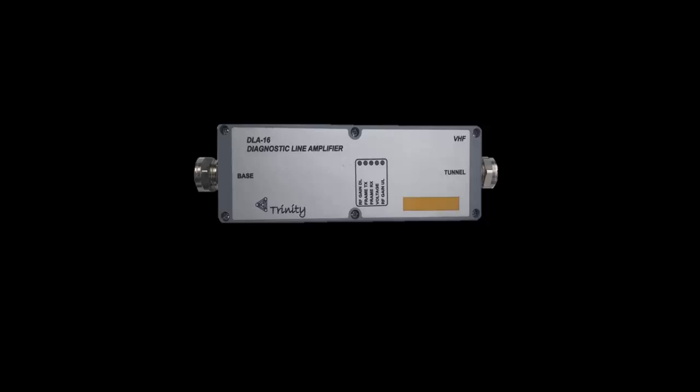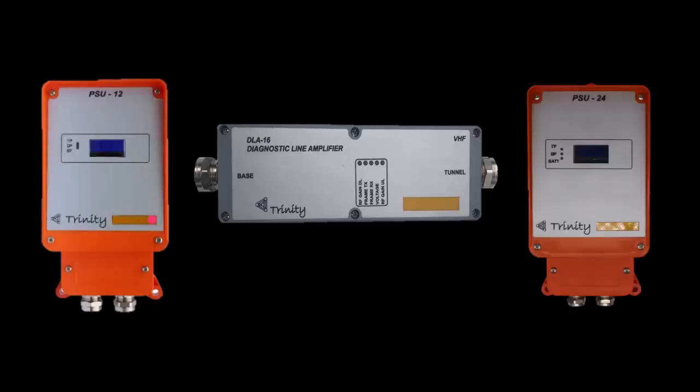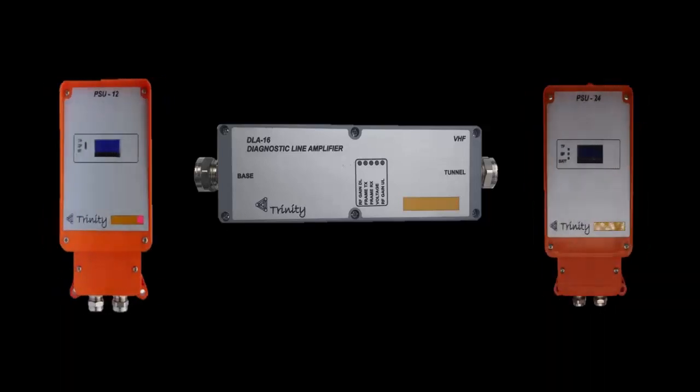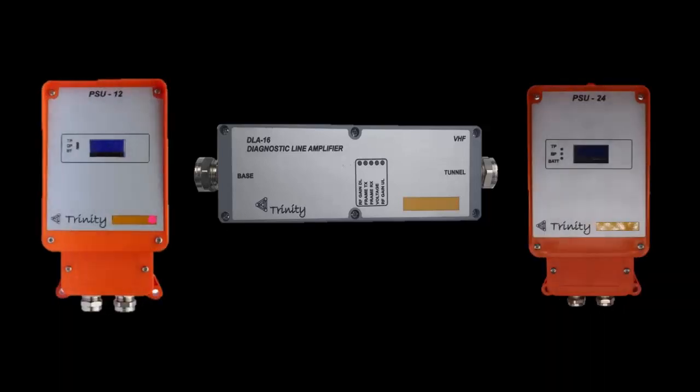The non-IS amplifier has an operating voltage of between 7 to 36 volts. This amplifier can be used in any 12 or 24 volt system with normal Trinity or other brands of Leaky Feeder power supplies with battery backup.